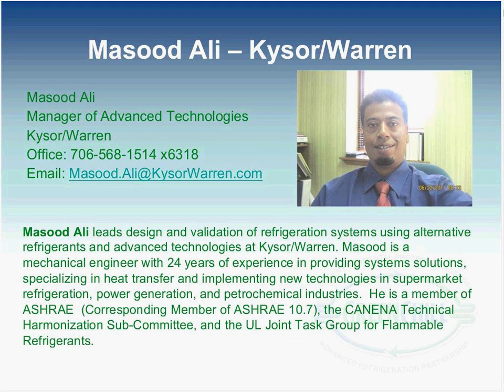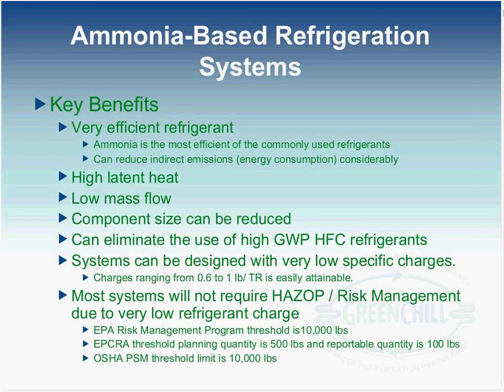Thank you, Kelly, and good afternoon, ladies and gentlemen. This whole session is laid out very logically, and as Scott has just mentioned, how these stores are configured with this CO2 secondary and direct expansion system. We have always talked about, you have heard about the secondary systems using glycol, CO2, and we talked about conventional HFC refrigerant on the top side. Now, the ammonia-based refrigeration system is going to cater to your top cycle refrigerant requirement that is predominantly used with HFC. This system is going to be a pure indirect refrigeration system.